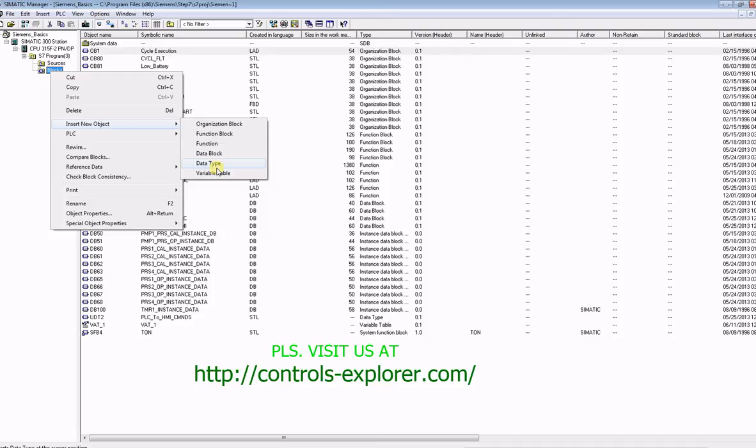So the data structure you create only once in a UDT, and then you create multiple DBs or a single DB, and call the UDT multiple times as per pump 1, pump 2, and pump 3.